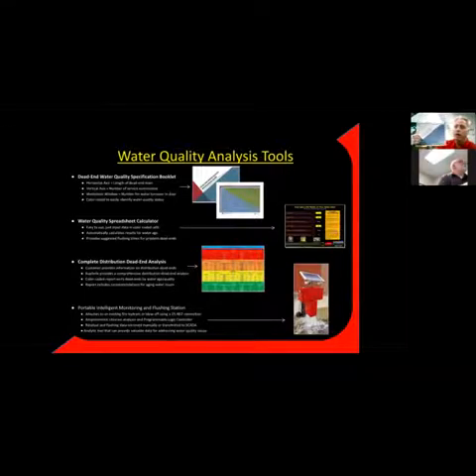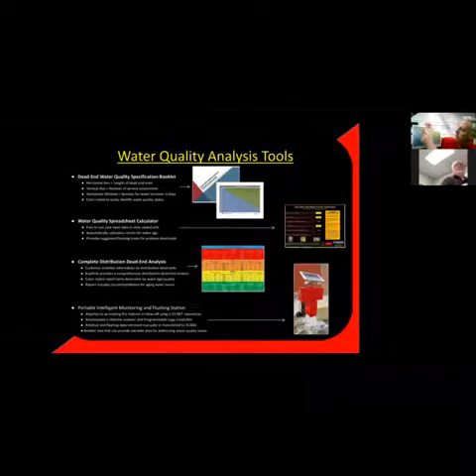Basically, an automatic flusher acts like additional houses on the line that turn the pipe over within a week's period of time, ensuring old water is replaced. This is a copy of the paper version of that tool — every page is a pipe size, with tabs for four-inch, six-inch, and so on. Along one axis is the number of service connections up to 35; along the top is the pipe length up to five miles by tenths of a mile. If the corresponding cell value is larger than four, we recommend an automatic flusher.